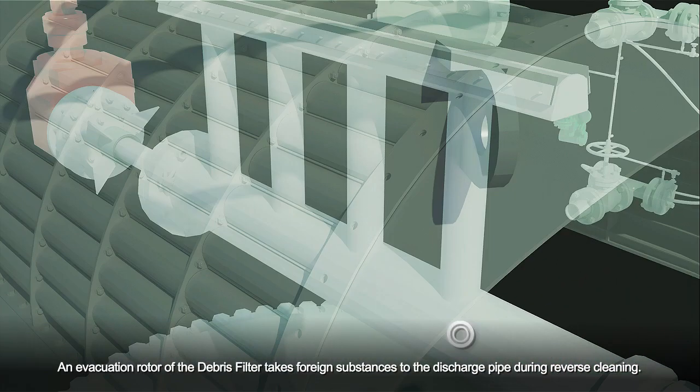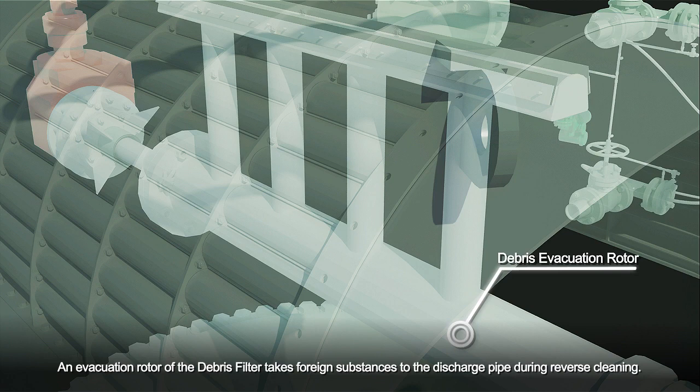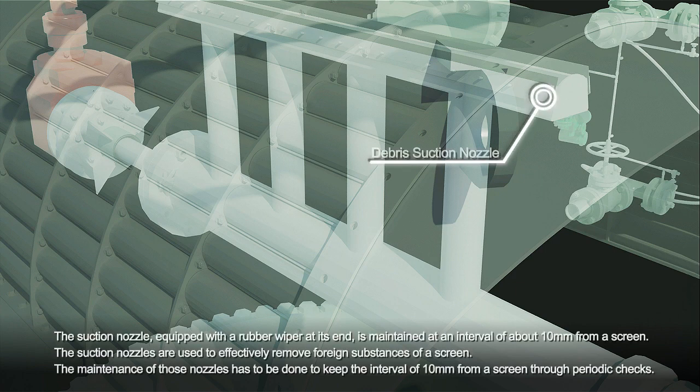An evacuation rotor of the debris filter takes foreign substances to the discharge pipe during reverse cleaning. The suction nozzle equipped with a rubber wiper at its end is maintained at an interval of about 10 millimeters from a screen. The suction nozzles are used to effectively remove foreign substances from a screen.